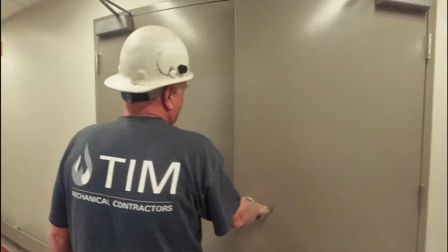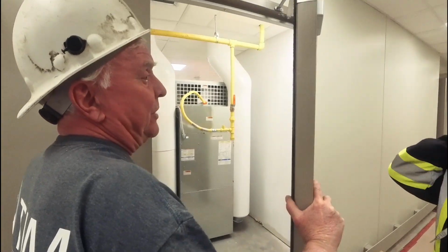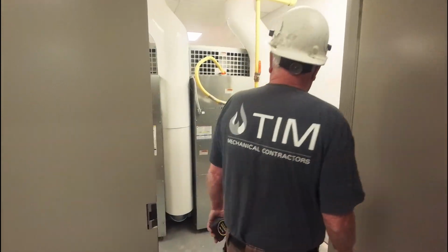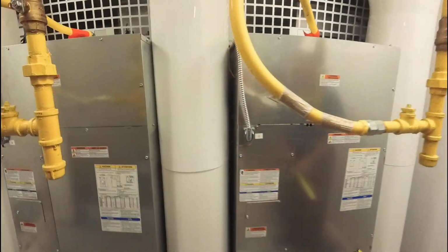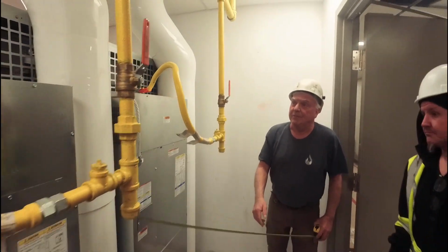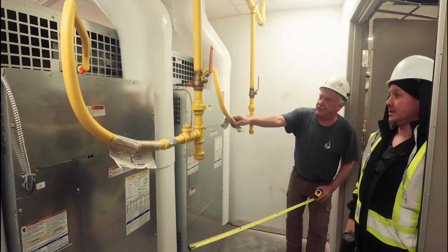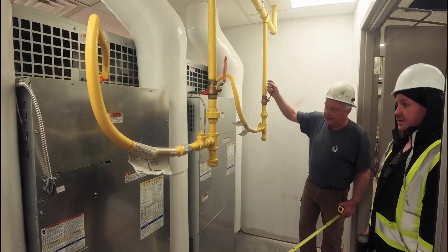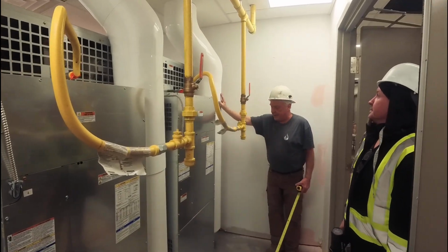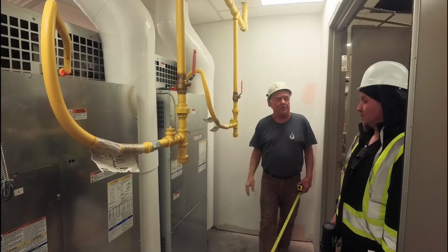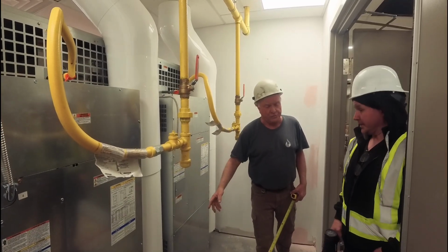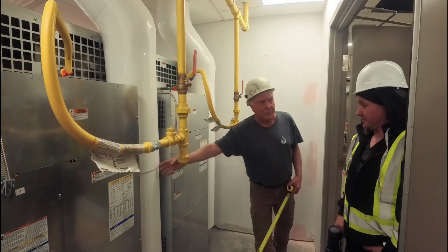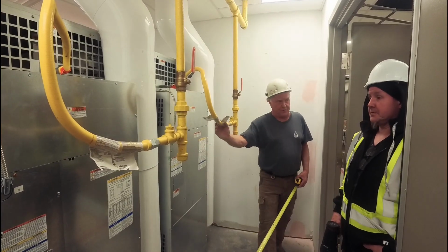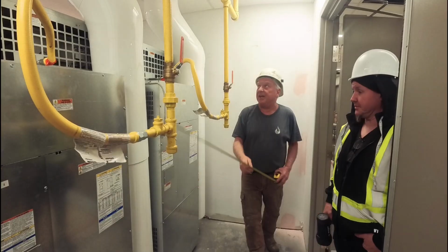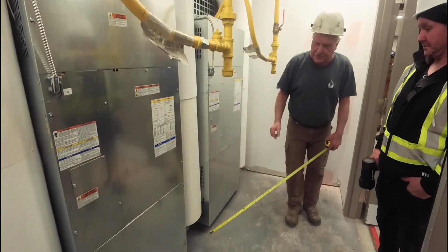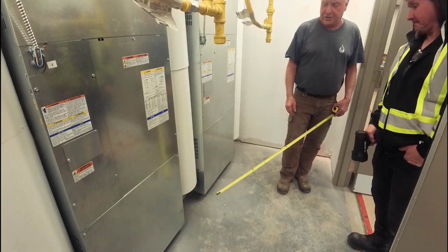The laundry is the next room we're going to look at. Before we go in the room, we'll just show you the exhaust on the dryers. It's natural gas dryers. As you can see, there's your gas vents, your valves again. These are the exhausts coming out of the dryer. So that's actually exhausting the hot air that's being created by drying the clothes. Yes. And it's also mixed with the natural gas fumes, going all the way up. It's 8-inch round, and it's got 2 inches of fibrous, rigid insulation on it.